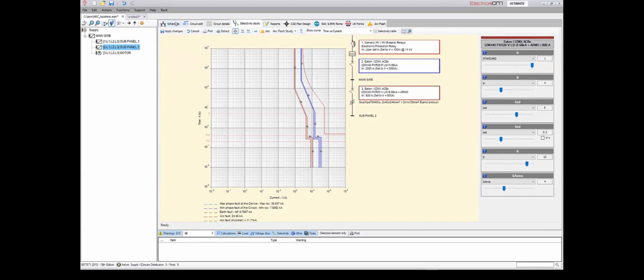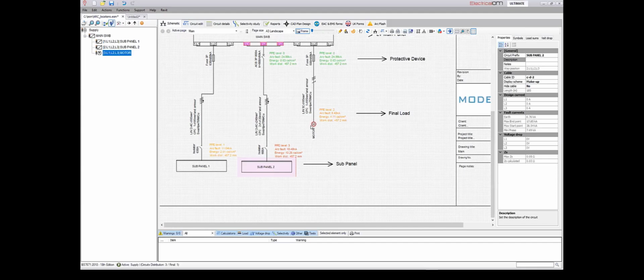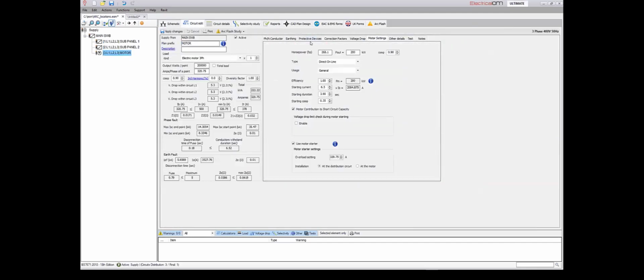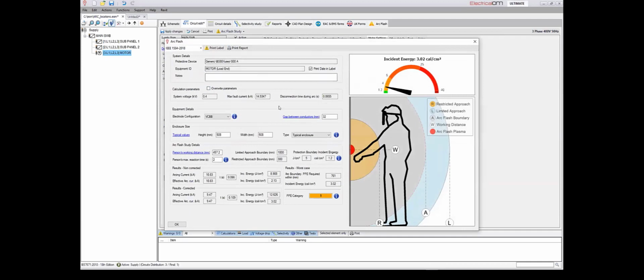Now, other options that are important to demonstrate here are the case where we may have, for example, a motor here, an industrial motor, and here we can consider the contribution to the short circuit capacity. So this will affect the fault levels, and as we've seen before, the fault levels affect the calculation of the arc flash incident energies. So it's very, very important to consider those options as well.